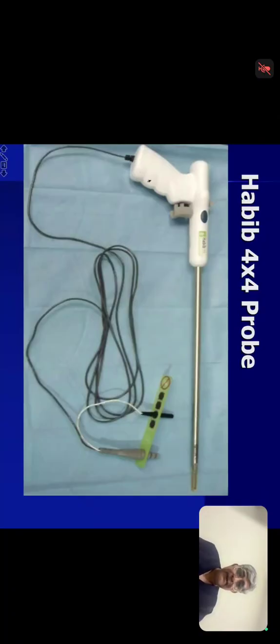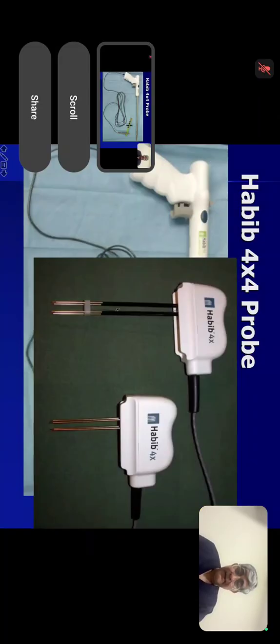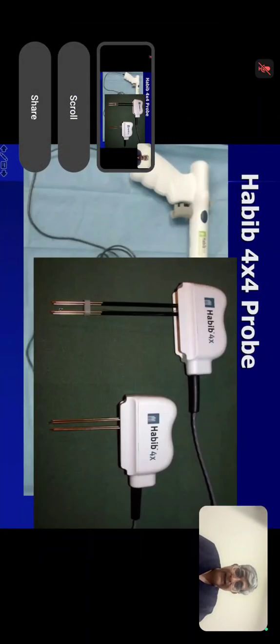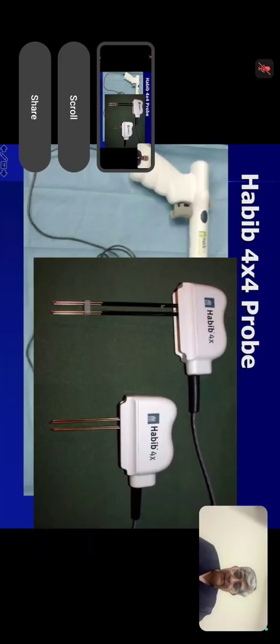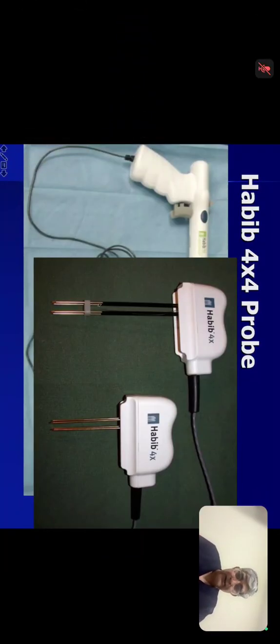So the probe is very, very simple, and basically it's got this set of 4. So it coagulates everything in between, and then the knife comes and cuts through. So it's completely brainless. You just put it into the tissue, cook it, and the knife will come and divide it. So even for open surgery, you can use a similar thing if you want to practice. It's an easy tool to use, and just divide. Just keep doing it like that, and you're done without even looking at any vessel.